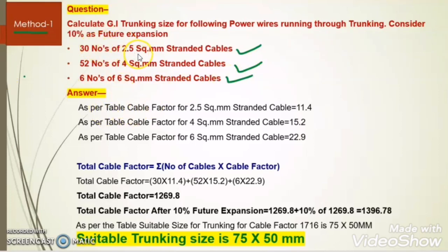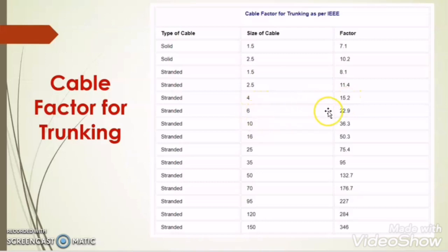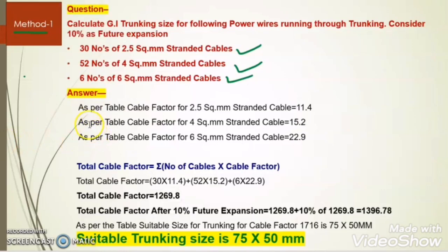Here there are 3 types of wires: 2.5 sq mm, 4 sq mm, and 6 sq mm. From the chart we get the factor for these 3 sizes of wires. The factor for 2.5 sq mm wire is 11.4, for 4mm wire is 15.2, and for 6 sq mm wire is 22.9.